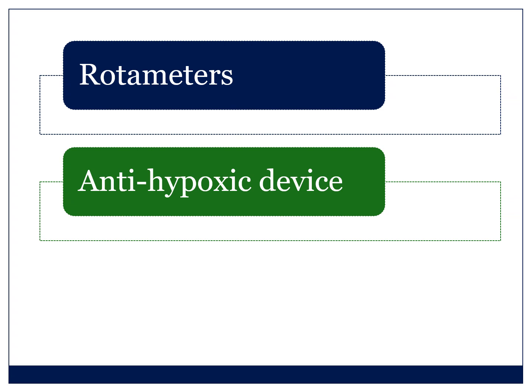The next thing you need to do is check your anti-hypoxic device. So this prevents patients getting hypoxic gas mixes. So basically what should happen is when you open nitrous oxide, the oxygen bobbin should also rise. So it prevents you giving pure nitrous oxide. And then when you close the oxygen, that nitrous oxide bobbin should fall. Now we're using nitrous oxide less and less in all hospitals, but if your machine does still have this capacity and you have nitrous, this is one of the tests that you need to do.